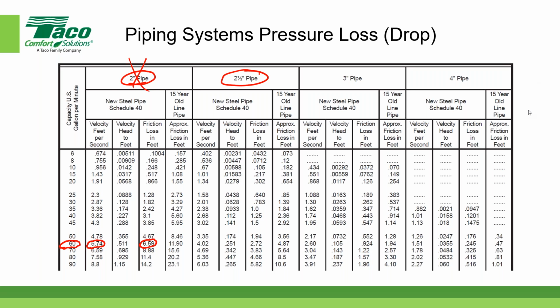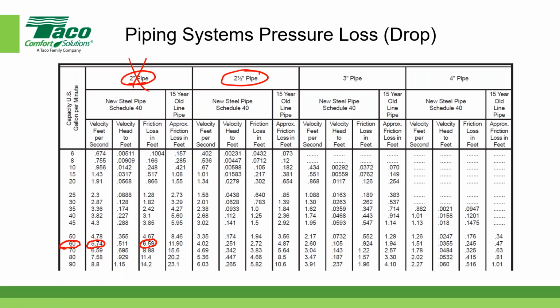No problem. So at 2.5-inch, look at the velocity. Well, it's less than 8 feet per second, which you would expect. Ooh, what happened here? Let's go back. Yep. It's still writing. So if you'll notice, it's 4.02 feet per second. So it meets the criteria of less than 8 feet per second. And the pressure drop is now 2.72 feet per 100 feet. So that means that it meets the criteria of 4 feet per 100 feet. So we've met both criteria. We've met the velocity, we're less than 8 feet per second, and we're less than 4 feet per 100 feet for the pressure drop. So the 2.5-inch pipe is the correct size.